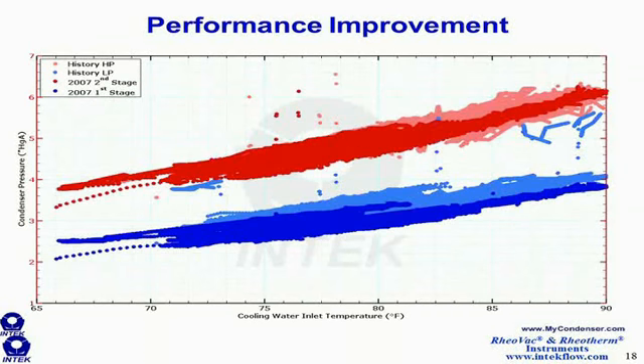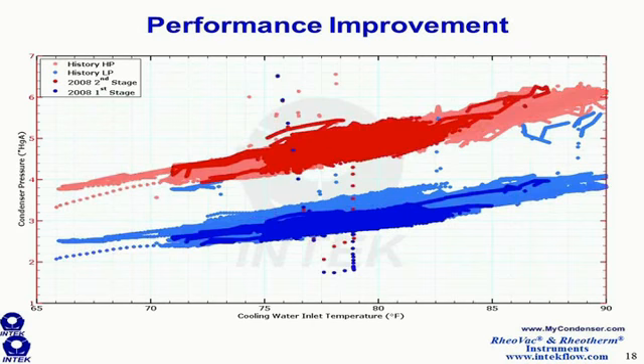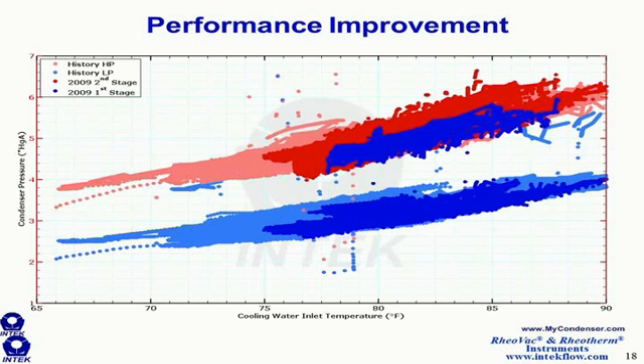Here's data for 2007. I faded the data from 2006 into the background. This is the entire year of 2007. This is the year 2008. This is the data from year 2009, and you can see some of the first stage pressure up at the second stage pressure. This is because they had an isolation failure between the two shells that caused the first stage shell to operate at the second stage pressure.